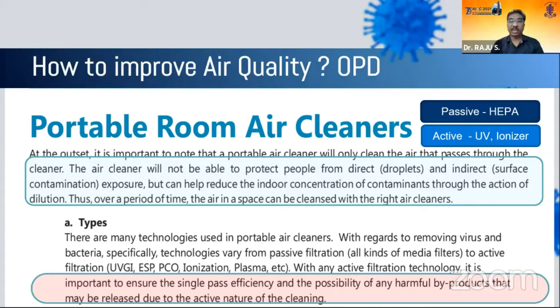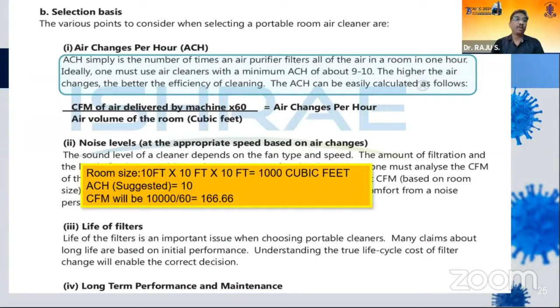As far as air filters are concerned, another important point that we should all consider when buying an air filter or a fan filtering unit is the CFM of that machine. So for a room size of 100 square feet with a roof height of 10 feet, the suggested air changes are approximately 9 to 10. So you should look at this value. You require about 166 CFM for that machine. For most OPDs, the size will be 12 by 12 or 12 by 15. So for that size of OPD, make sure that you have a machine with a mentioned CFM value of 240 to 300. So when we are buying the machine, we have to look at this particular specification and then buy it.